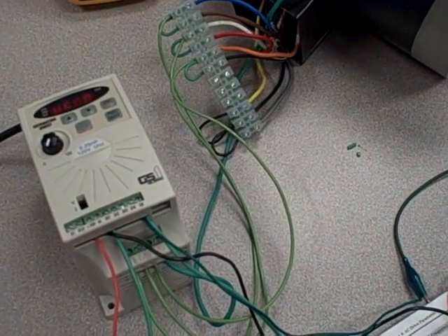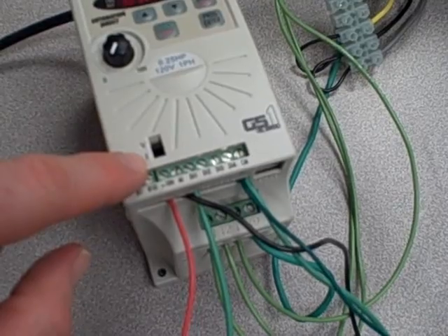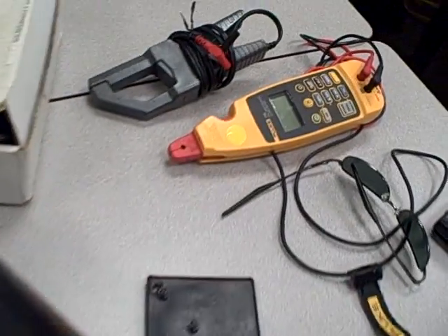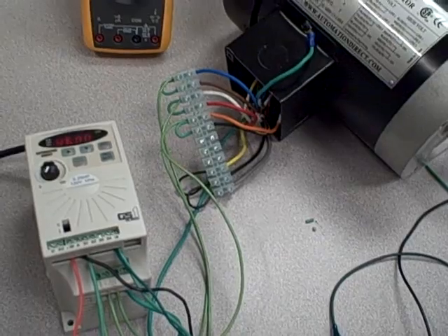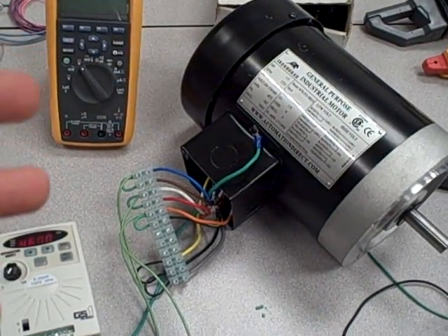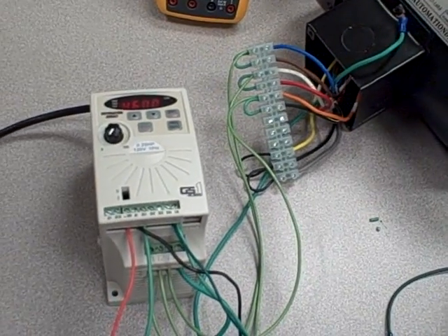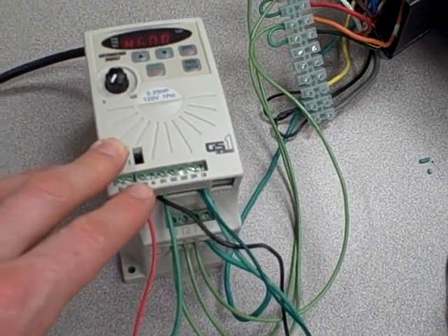One of the other options we have that we don't have hooked up right now is we could flip that switch into the I setting and be able to accept a current input from a source like a 4 to 20 milliamp loop calibrator, or ideally the output of a loop controller. And that way this motor now is a final control element that can be throttled anywhere between 0 speed and full speed in lieu of throttling a control valve, a throttling valve. So we can also do that in process control systems using standard 4 to 20 milliamp signals.